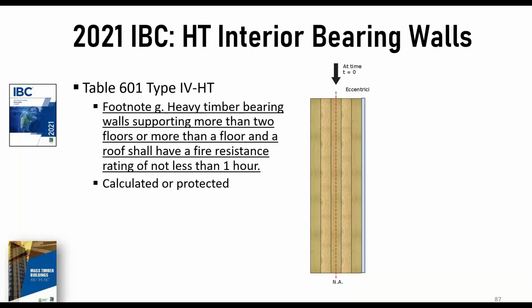In fact, the members of the Tall Wood Building Ad Hoc Committee were emphatic that the structural strength of the mass timber elements themselves contribute to the inherent fire resistance of the building. The code change works out to be 2/3 of the fire resistance is provided by non-combustible protection, typically gypsum wallboard or drywall. The other 1/3 has to come from the inherent fire resistance of the heavy timber elements themselves. So in this little example here, we're going to show you, we'll go back there, we have some non-combustible protection there in the form of gypsum wallboard on the exterior, or we can have it bare.